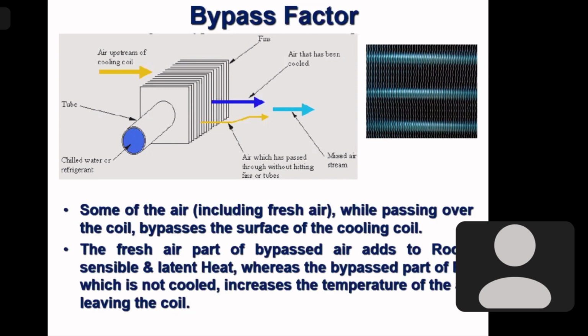So part of that also bypasses. That part of the outside air comes to the room directly through the ducting. So it adds heat load in the room directly. It adds both sensible heat, by the high temperature of 42 or 43 degrees centigrade a few days back in Calcutta, and also the moisture part. Calcutta is very famous for its humid weather. So the outside air has high humidity, a high moisture level. That moisture brings in latent heat along with it when you take the outside fresh air. You want fresh air for oxygen, but along with that you get bonus heat and moisture, which is a bonus problem. So you have to tackle that problem.